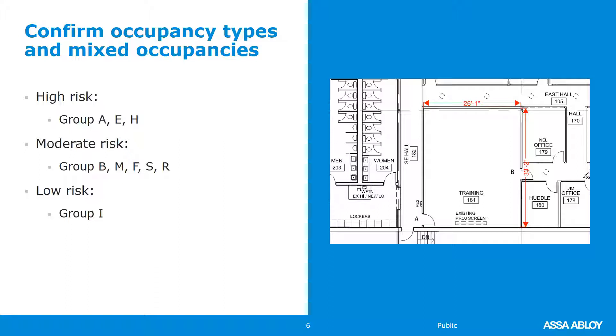A lower-risk occupancy type is Group I Institutional, where you have staff and the people are not capable of self-preservation — detention or correctional facilities, hospitals, nursing homes, assisted living facilities. Because of the presence of staff and mandatory full sprinklering, they're considered lower risk, and you are able to lock the door on the egress side in those types of occupancies.